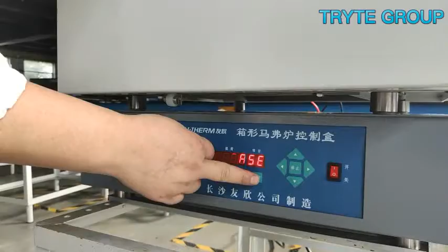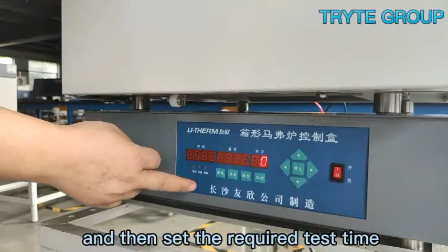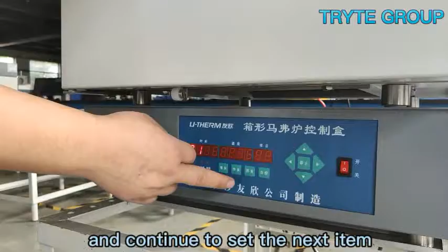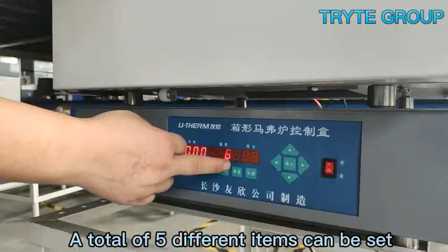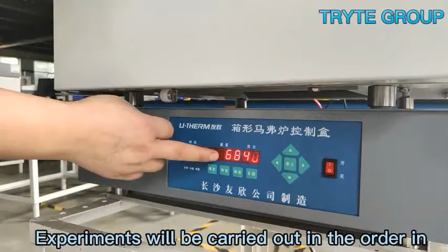If you need to set the test items independently, you can press the autonomous button, and then set the required test time and temperature according to your needs. Press the button to save, and continue to set the next item. A total of 5 different items can be set. After starting the test, experiments will be carried out in the order in which they are set until the 5 items are tested.